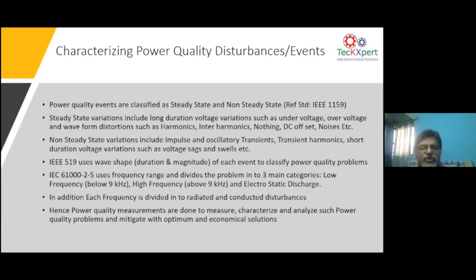IEC 61000 looks into the frequency content of the power quality. When it is a voltage or a current, it has a certain frequency content. This frequency content in the harmonics range goes up to about the 200th order, that means around 9 or 10 kilohertz. Up to that level you can have harmonic currents. But as you go to higher orders, you will have more noise, and it could be either conducted electromagnetic phenomena, or, as the frequency goes up, the cable will start radiating, so you'll have radiated electromagnetic phenomena. So frequency is another aspect of characterizing it.